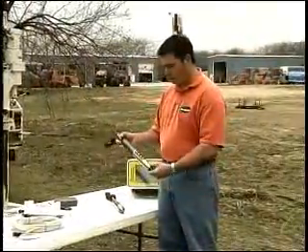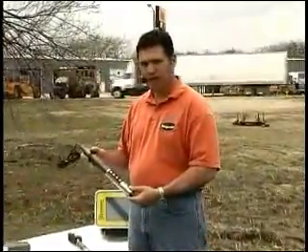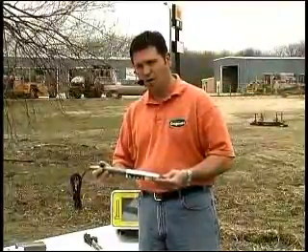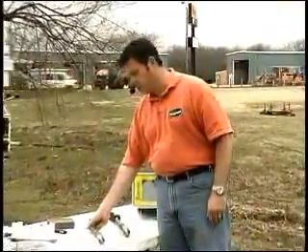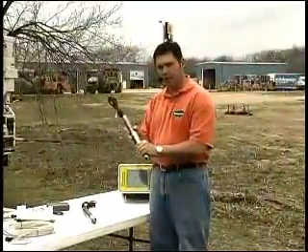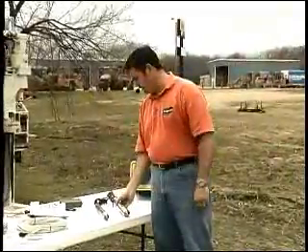The SC400 probe is the one many people use today with 1¼ inch rod systems. Both of them you can see are about 1 foot long. This one's 1½ inch diameter, connecting to 1¼ inch diameter probe rods. This one is 1½ inch diameter on the fattest portion, connecting to 1½ inch diameter probe rods.